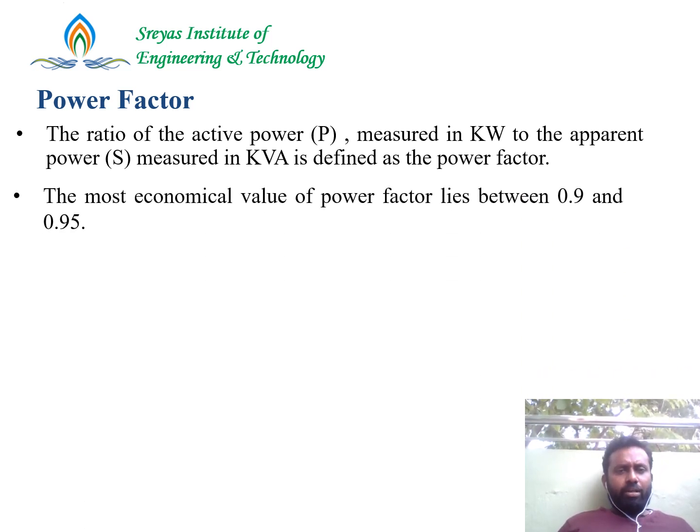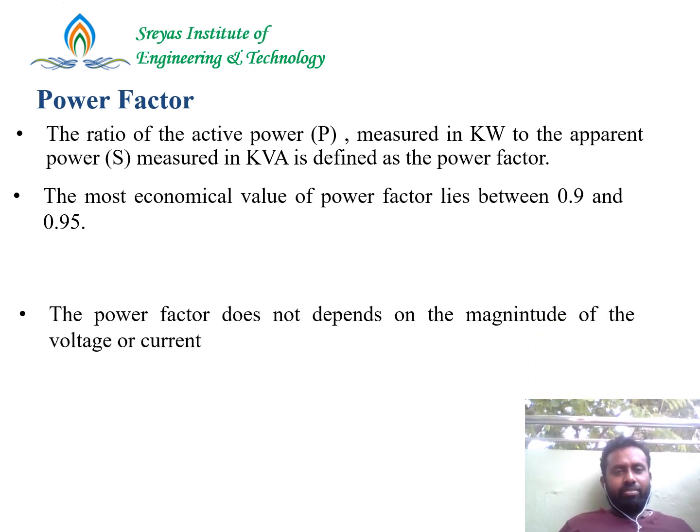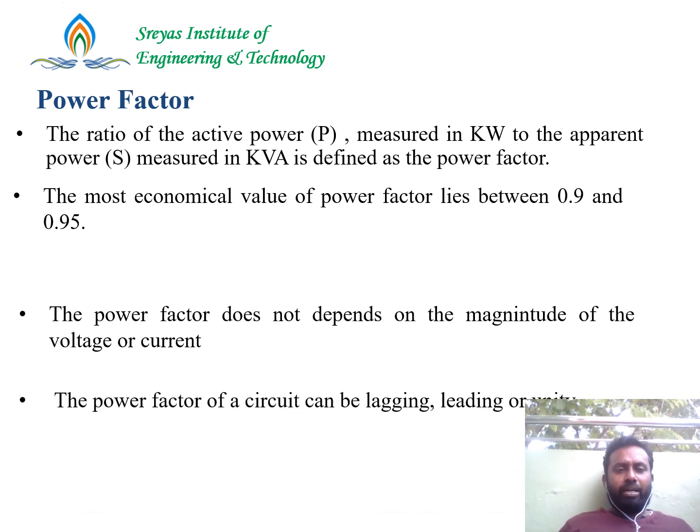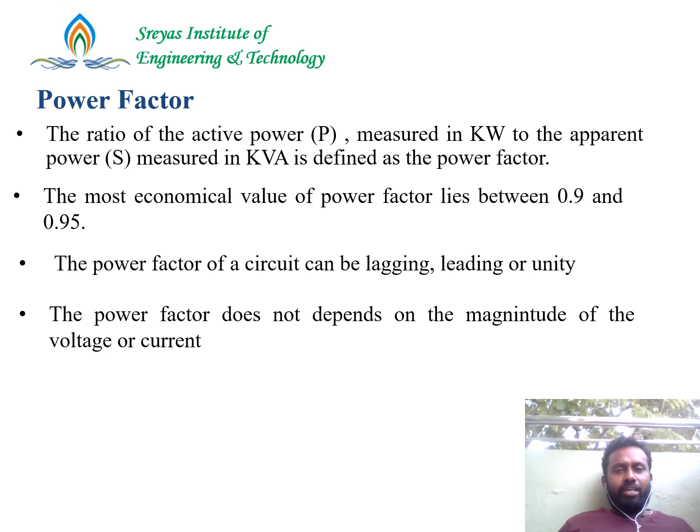The most economical value of power factor lies between 0.90 and 0.95. The power factor does not depend on the magnitude of voltage or current. The power factor of a circuit can be lagging, leading or unity.